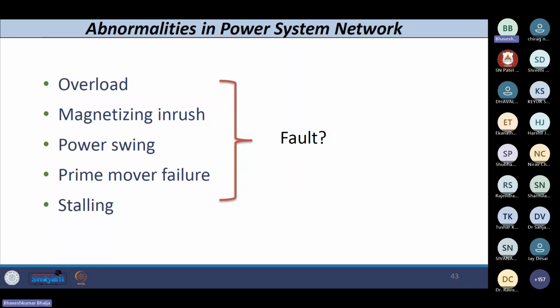Let's say there is a fault on an adjacent line. Obviously your neighboring line is also affected, and its voltage and magnitude change. This should not be detected as a fault. It is not a fault. Power swing is going to die out after some time. It has some specific locus. Usually this locus moves from, let's say, the first quadrant to the third or fourth quadrant, depending upon the situation. So that is also there, but this should be discriminated from the fault condition.